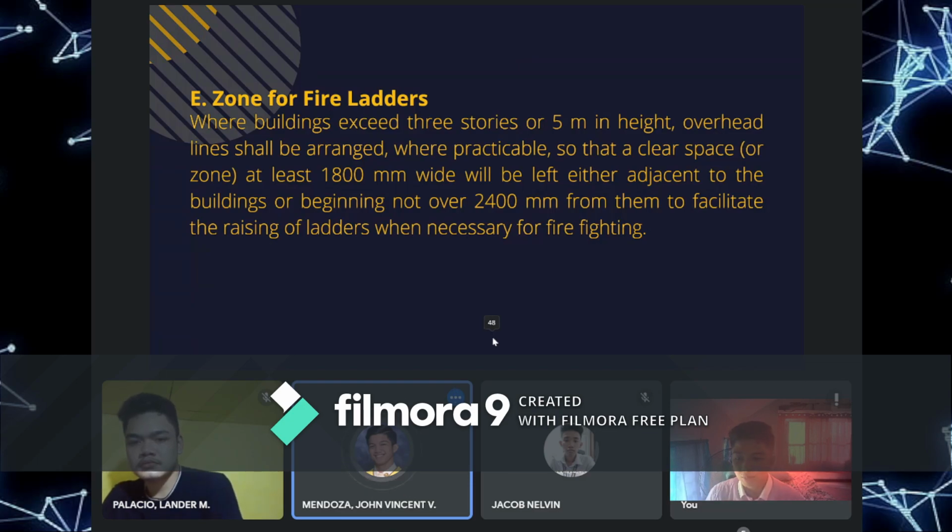So para sa mga structures na malalaki, dapat yung allowance nila between the building and the wire ay dapat more than 1,800 millimeter and 2,400 millimeter. Para ito sa mga ladders in case of fire sa building and other situation like maintenance ng window sa malalaking building.